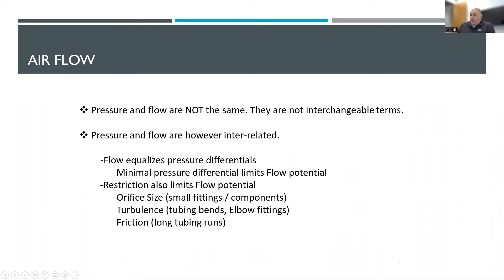When designing an air system in a plant or around a machine, restrictions matter. How you pipe it — the number of bends, narrowing in the tube, or going down into an orifice — creates restriction in the flow, minimizing the amount of flow you get. There are also friction forces involved in fluid flow, especially with very long tubing runs. For those of us more electrically minded: friction equals resistance. The longer your cable runs, the more power is lost in that run — the same thing applies to pneumatics.